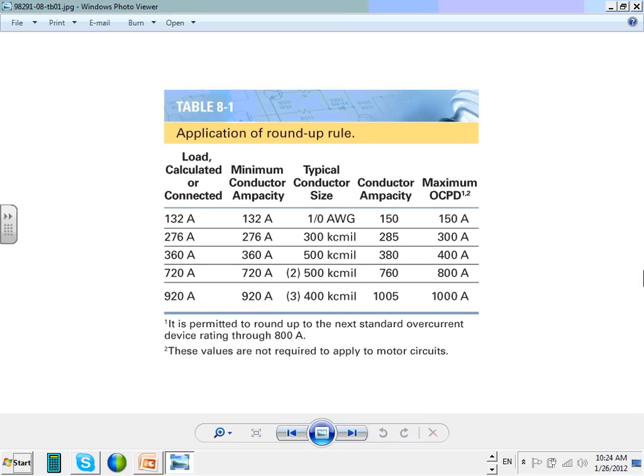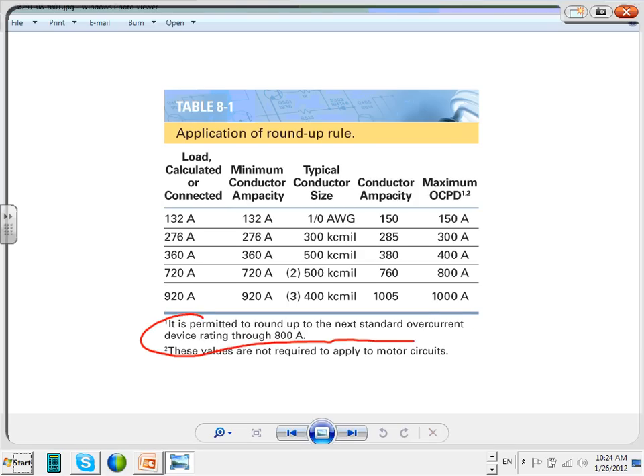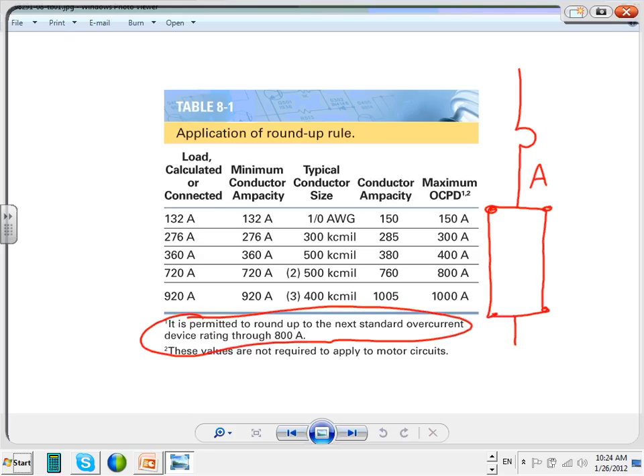Rounding up conductor. Okay, typical. I just want to highlight this one for rounding up, guys. You can round up to 800 amp. And I will use this example and stop right here. I always use this example. This is phase A only. I'm paralleling conductors and tying them to an equipment. I'm using 500 kcm here and 500 kcm here.